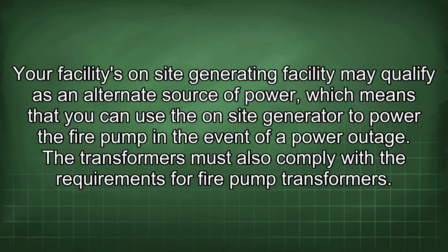Your facility's on-site generating facility may qualify as an alternate source of power, which means that you can use the on-site generator to power the fire pump in the event of a power outage. The transformers must also comply with the requirements for fire pump transformers.